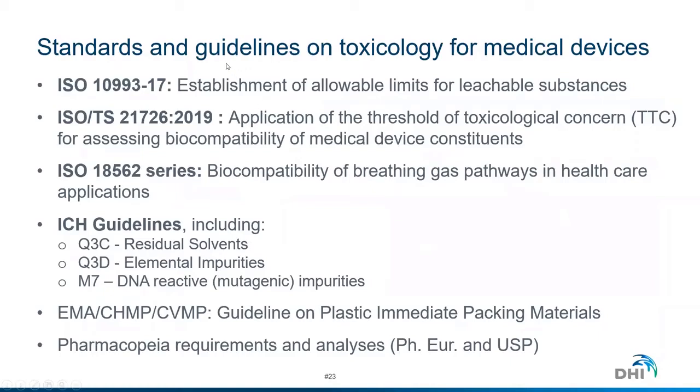And how to do that? There are a number of standards to work with when you do toxicology for drug delivery devices. There's ISO 10993-17 that describes how to establish the allowable limits for leachable substances and substances in the medical device. There is the standard ISO 21726 on the application of the threshold of toxicological concern when you assess medical device constituents or leachables. There's the ISO 18562 series that describes how to test for migrating substances that can enter from the device into the liquid or the gas when you have an inhalation device.